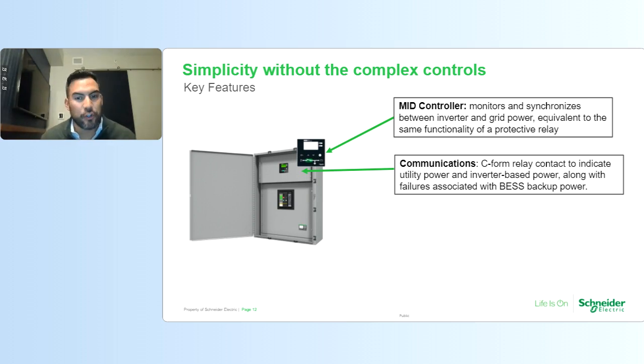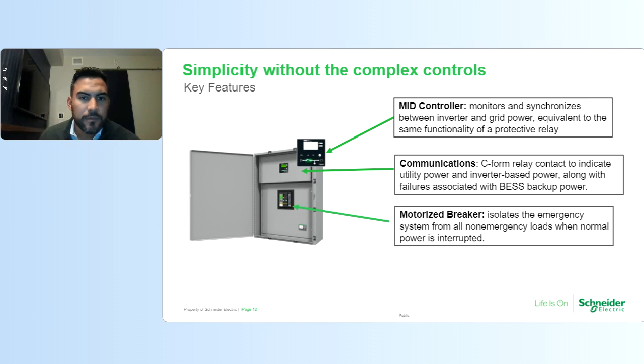Additionally, when utility returns, that breaker remains open, and then we signal again the energy storage system to change state from grid forming to grid tied. So essentially, if you look at SourceBack, it has a very basic microgrid controller and the actual hardware of the electrically operated breaker to disconnect from the grid. It comes with the electrically operated motorized operator, so it isolates the emergency system from non-emergency loads when normal power is interrupted.